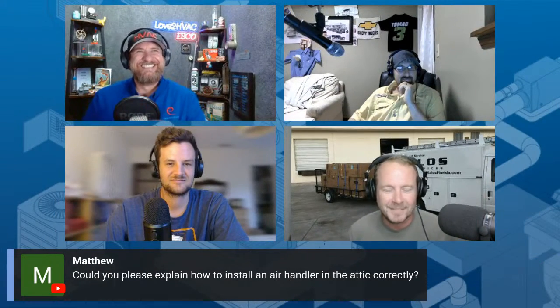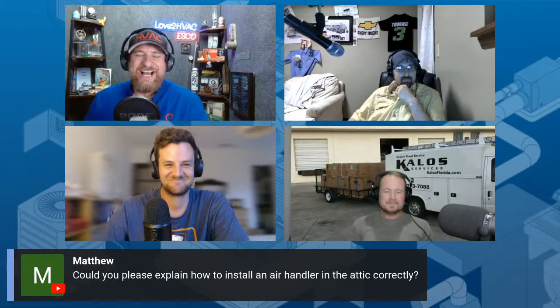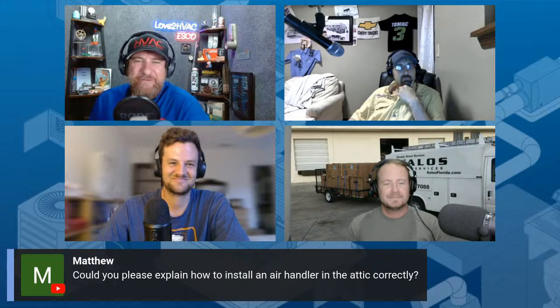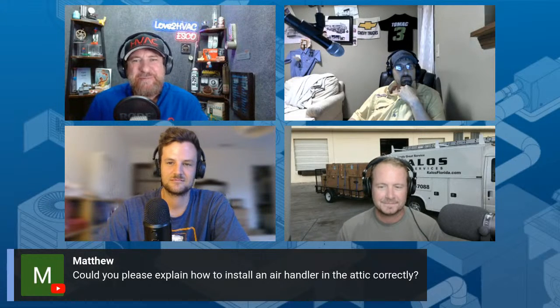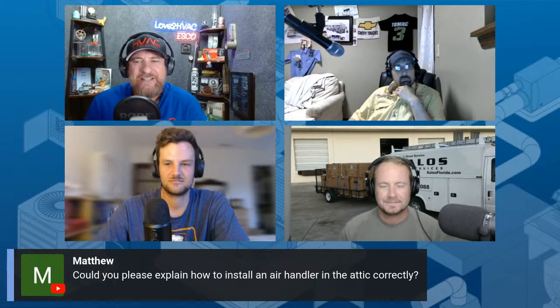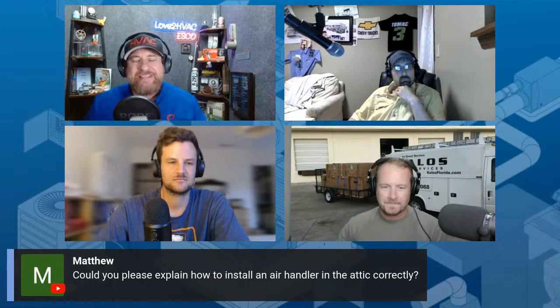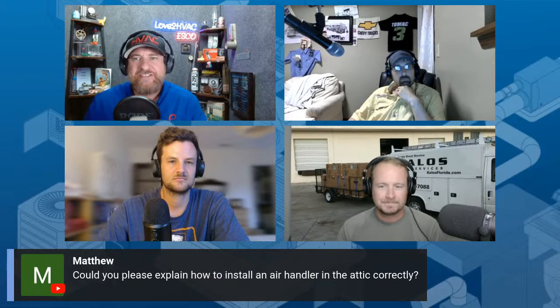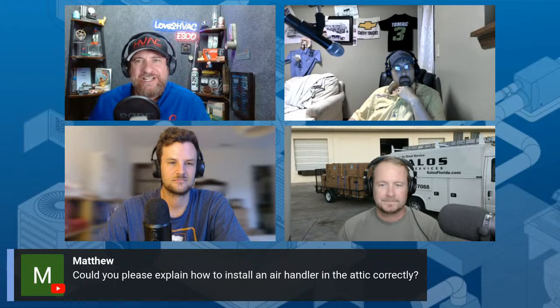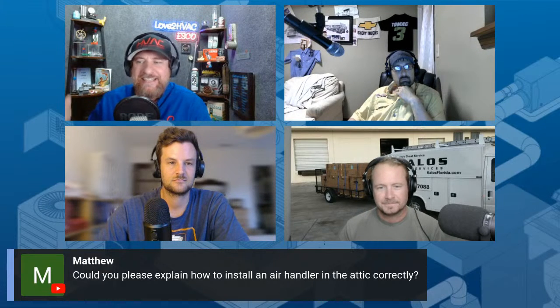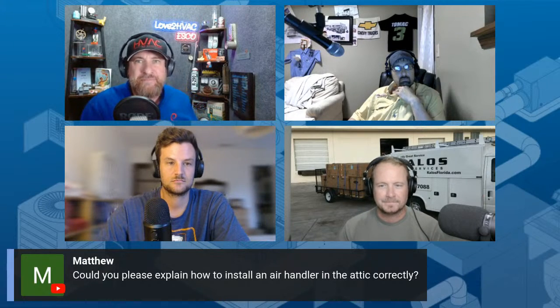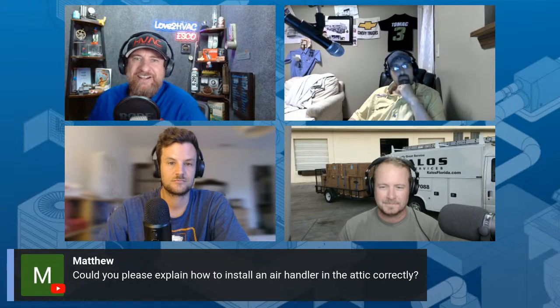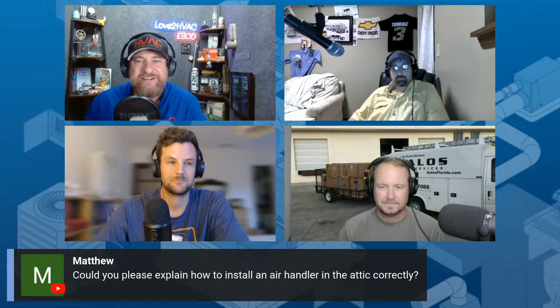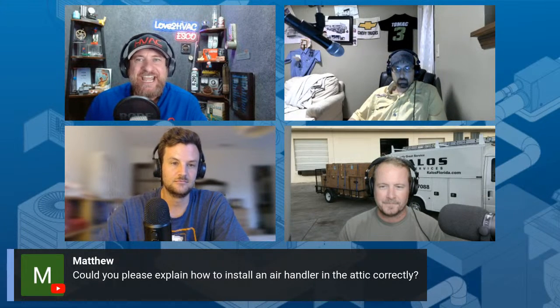Ty, do you have anything? RTFM - before you install it, read that manual. People ask me so many questions about it, and there's so much stuff in the manual, and I get it, I struggle reading too, but take a highlighter and break it down into little sections. Even like how the suction line, should it have a riser or not - that's actually in the outdoor manual, but that information's in there. And about the coil, which way it turns, air sealing, air flow.